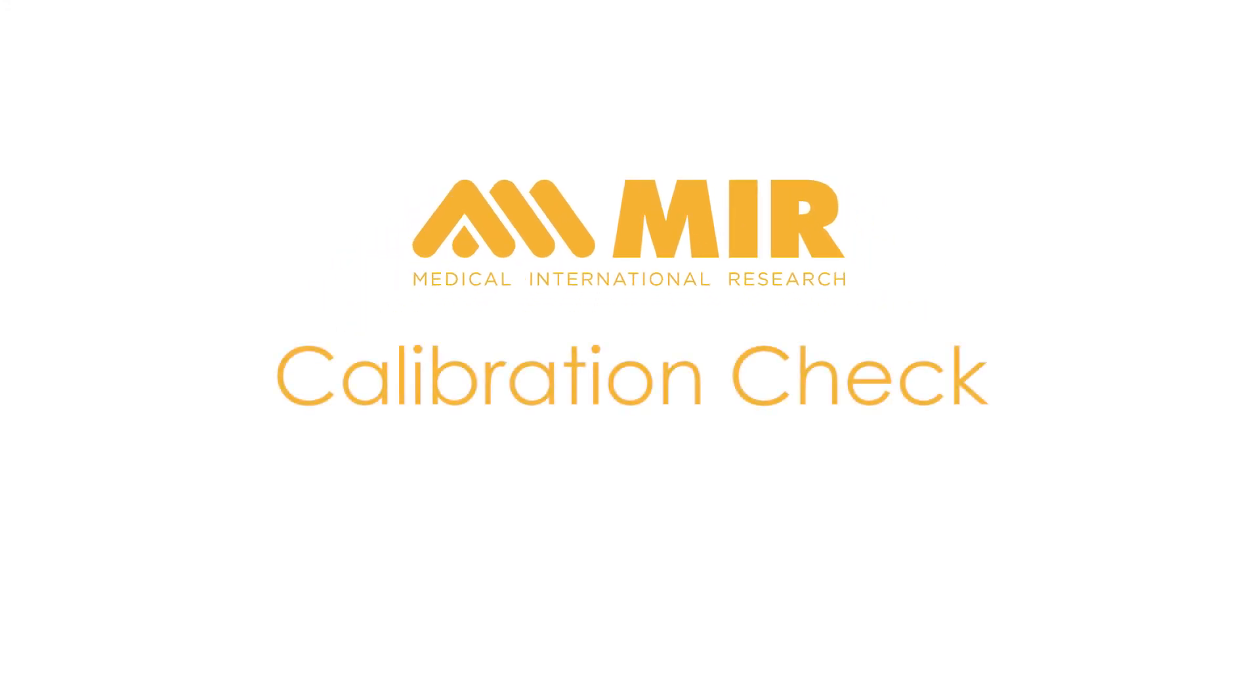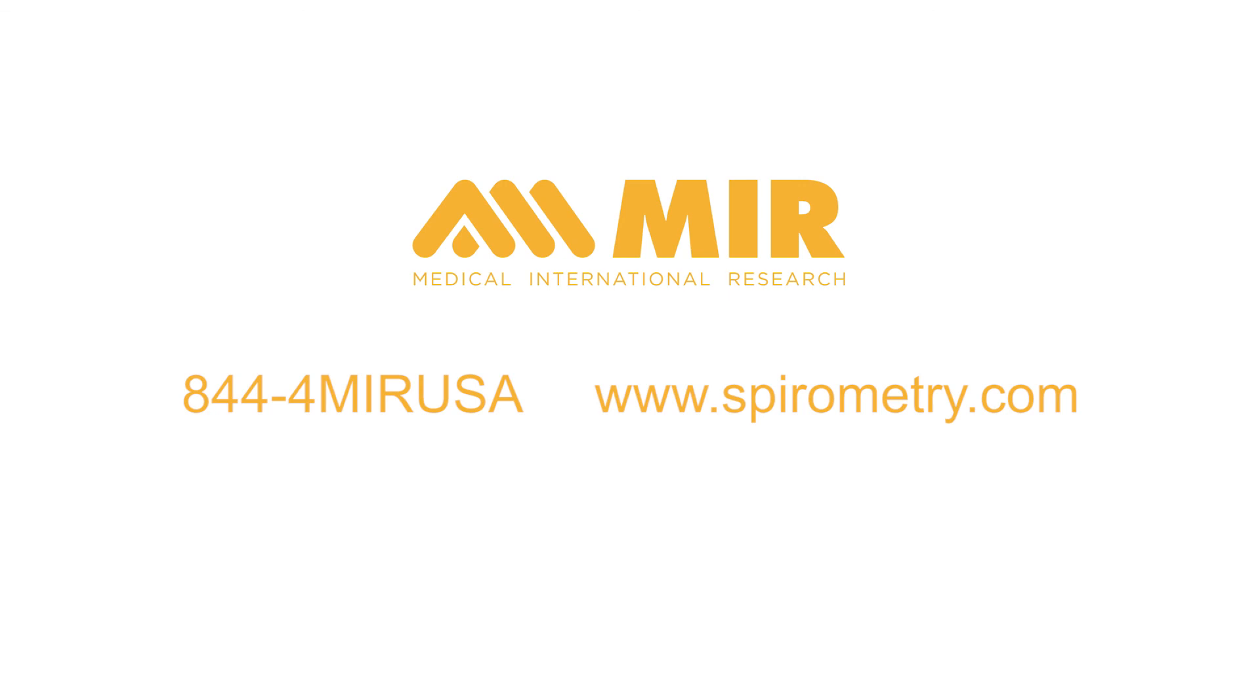This completes the procedure for doing a calibration check on an MIR spirometer with the three liter syringe. Thank you for your interest in the MIR spirometers. For more information, contact MIR at 844-4MIR-USA or you may visit our website at www.spirometry.com.